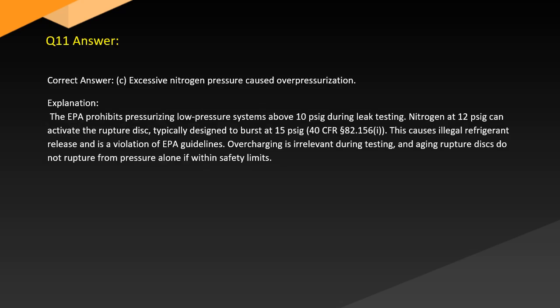Answer. Correct answer: C. Excessive nitrogen pressure caused overpressurization. Explanation. EPA prohibits pressurizing low-pressure systems above 10 psig during leak testing. Nitrogen at 12 psig can activate the rupture disc, typically designed to burst at 15 psig, 40 CFR 82.156. This causes illegal refrigerant release and is a violation of EPA guidelines. Overcharging is irrelevant during testing, and aging rupture discs do not rupture from pressure alone if within safety limits.